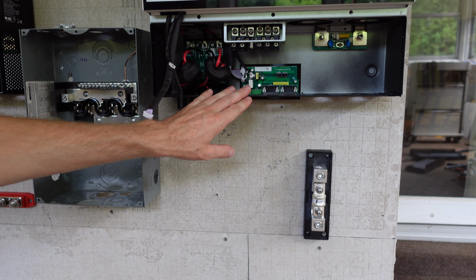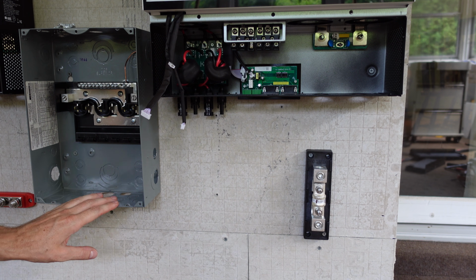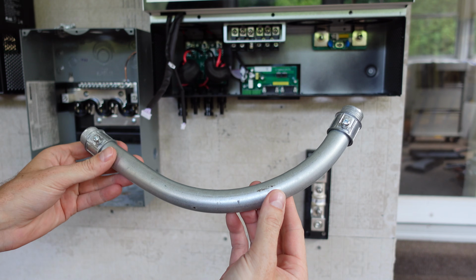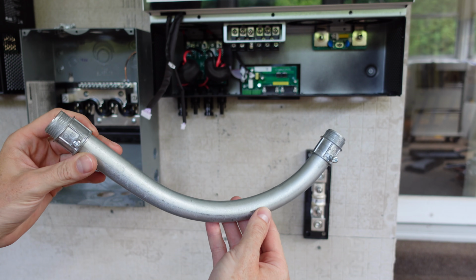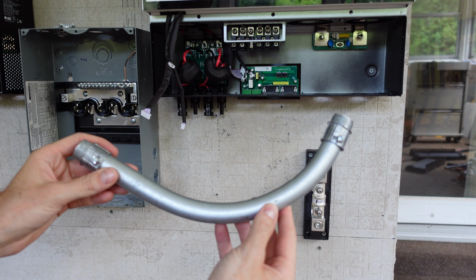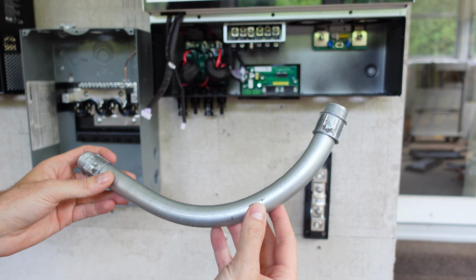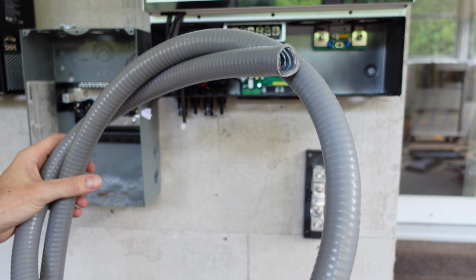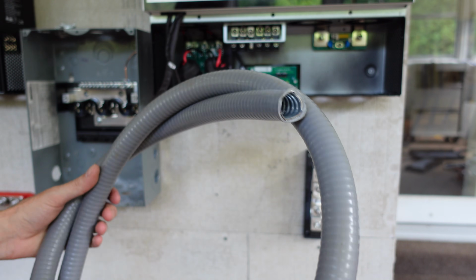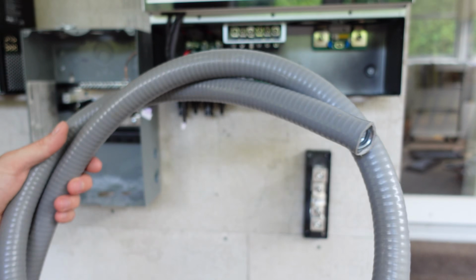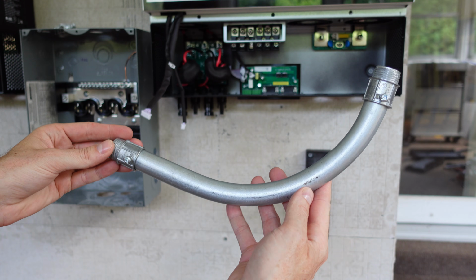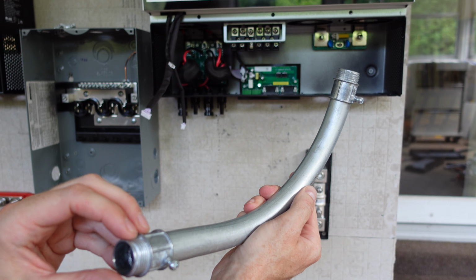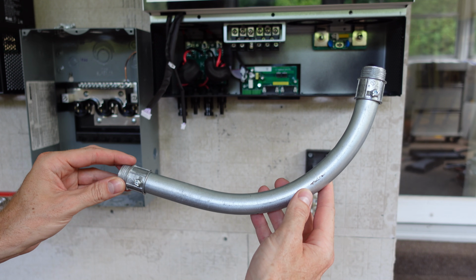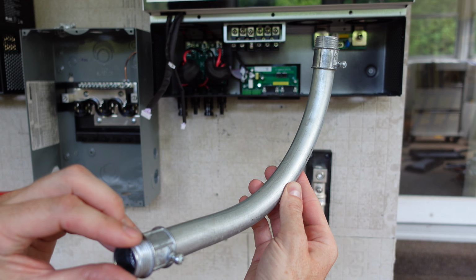Now, to run the AC output from this inverter down to this breaker panel, I'm going to use a piece of 3/4 inch EMT conduit. I guess EMT is technically tubing, not conduit, but I was going to use this liquid tight flexible conduit that I had from a previous project. However, the fittings for this are quite expensive, so I opted for the EMT, and my conduit bending skills are pretty good, but they're not perfect yet, so that's why it does look a little odd.